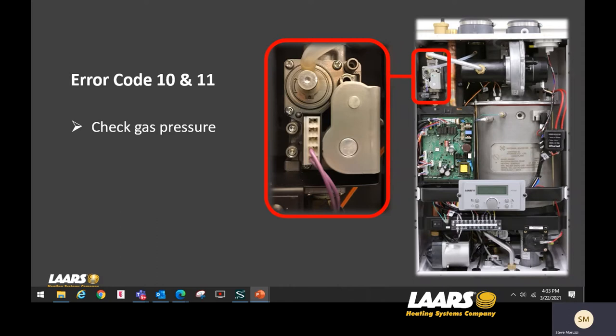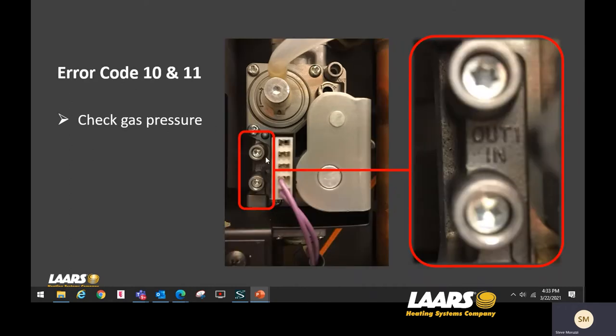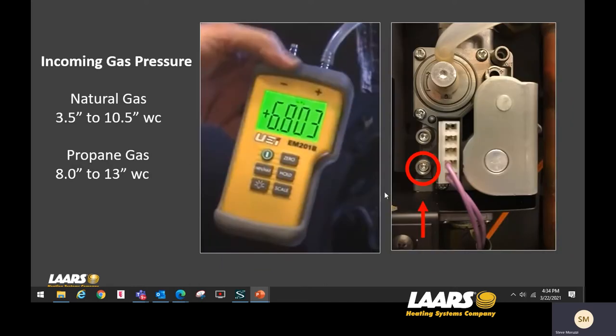We'll start with checking gas pressure. Here I'm showing a gas valve on a 140 model and its location on the wall-hung 140. On the gas valve you'll see two taps — one reads in and one reads out. Loosen your needle valve with the Allen key or Torx bit — just loosen it, don't take it out — and you can put your manometer over that and read your incoming gas pressure. Incoming gas pressure for natural gas should be between 3.5 and 10 inches of water column, and for propane, 8 to 13 inches.